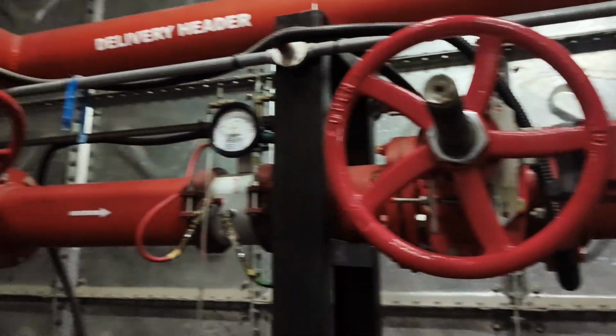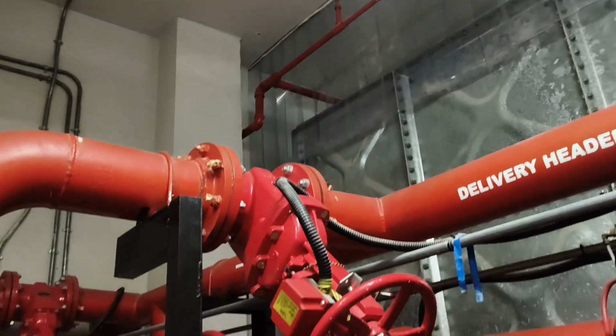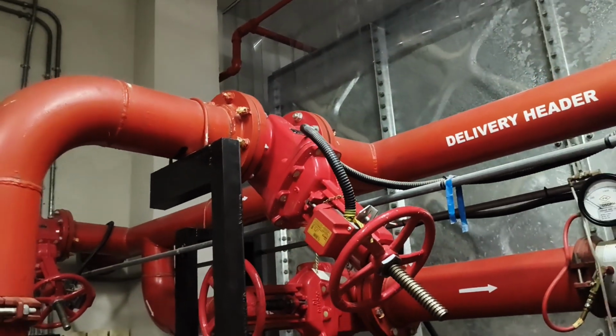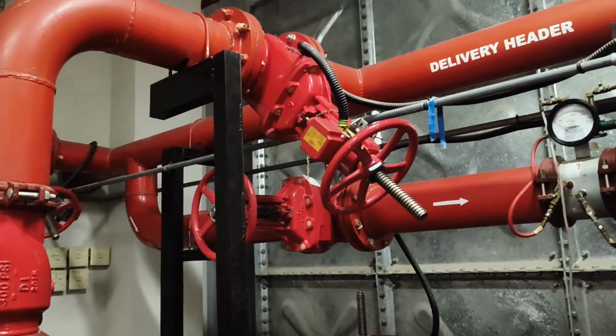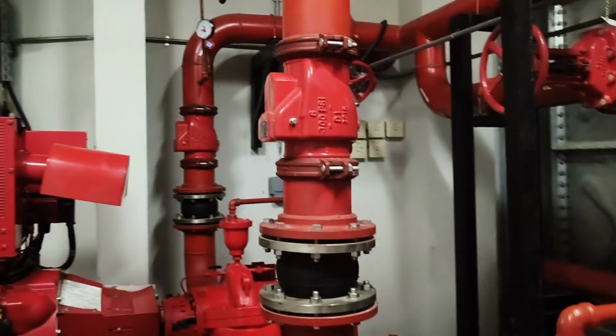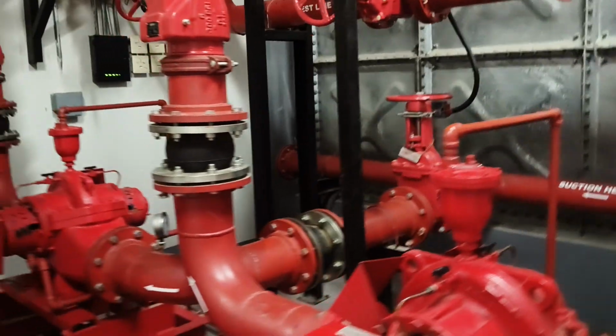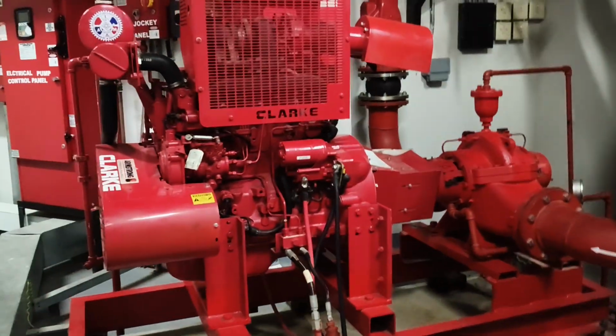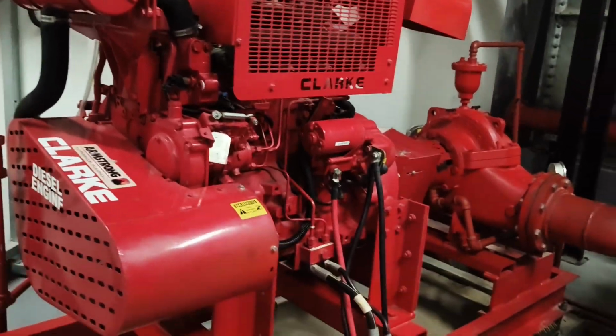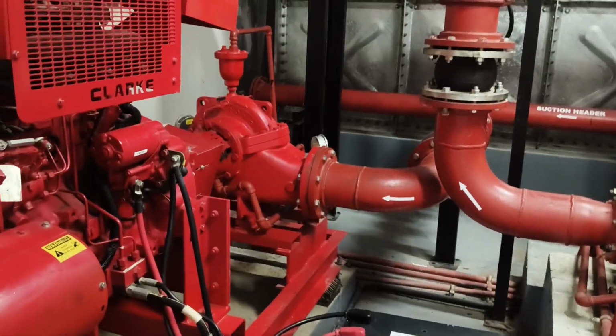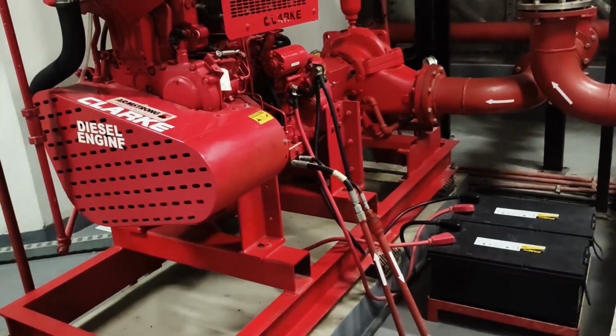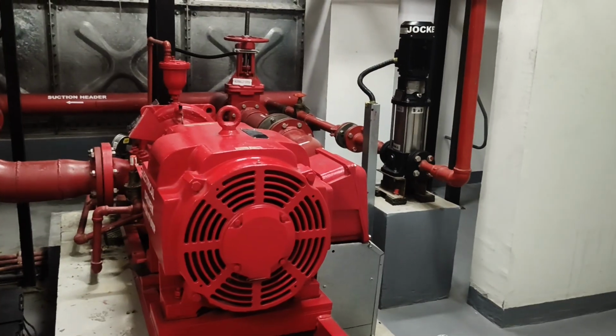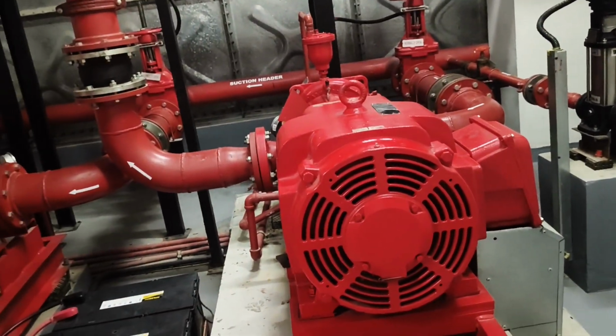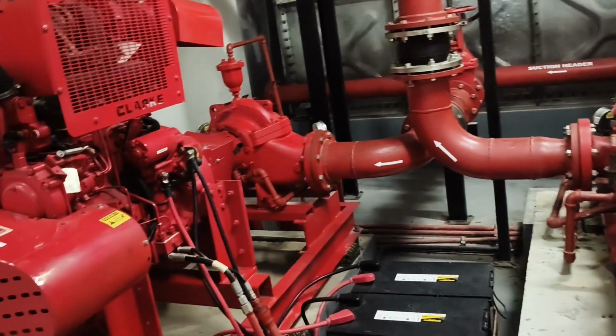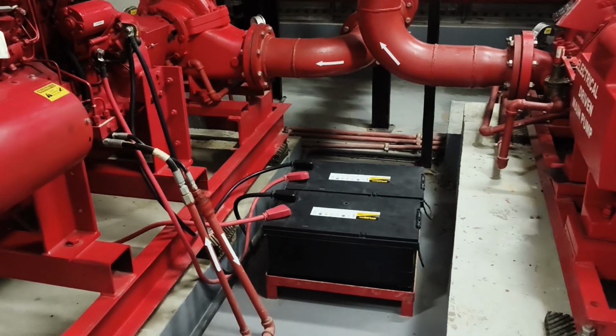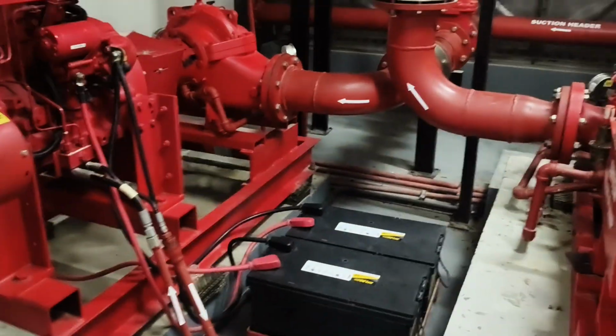This is actually the test line, and this one here is the electric's discharge gate valve as well. So whenever the pressure goes down, the jockey will start and this will follow, and the diesel is going to follow as well. But in case there is a power loss and there is no standby generator, the electric and the jockey, because they are three-phase and use power supply for their work, this is the only option, the diesel, because it has a standby battery. But that time this has to be able to sustain.